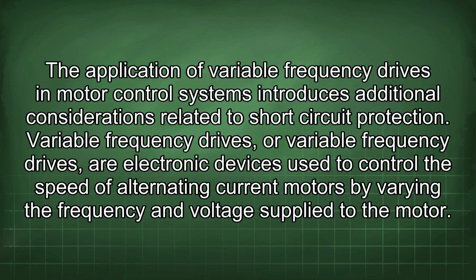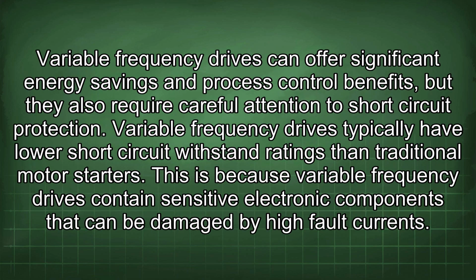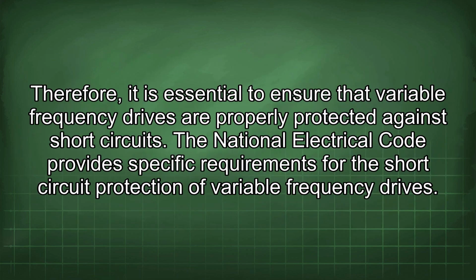The application of variable frequency drives in motor control systems introduces additional considerations related to short circuit protection. Variable frequency drives are electronic devices used to control the speed of alternating current motors by varying the frequency and voltage supplied to the motor. Variable frequency drives can offer significant energy savings and process control benefits, but they also require careful attention to short-circuit protection. Variable frequency drives typically have lower short-circuit withstand ratings than traditional motor starters. This is because variable frequency drives contain sensitive electronic components that can be damaged by high fault currents. Therefore, it is essential to ensure that variable frequency drives are properly protected against short circuits.